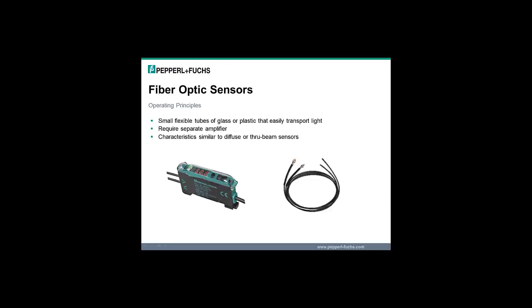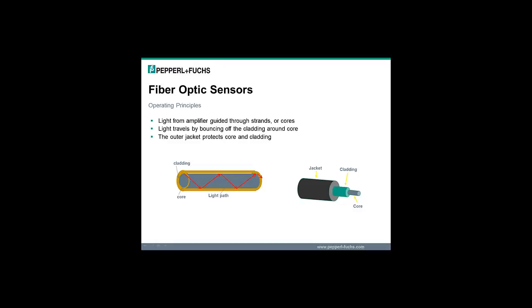Fiber-optic sensors require both fiber-optic cables and a fiber amplifier. Fiber-optic cables are small flexible tubes of glass or plastic that easily transport light. The fiber amplifier is a separate sensor that houses both the emitter and receiver, and the sensing characteristics of fiber-optics are similar to diffused or through beam mode sensors. Light from the fiber amplifier is guided through transparent strands within the fiber or cores by total internal reflection, traveling along the core by bouncing off the cladding wrapped around the core. The outer PVC or stainless steel jacket protects the core and cladding from damage.